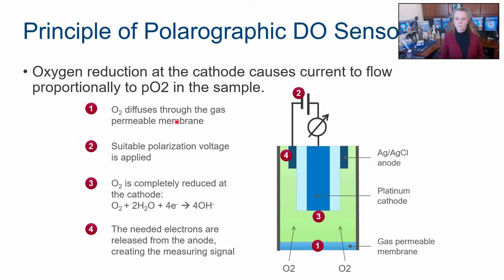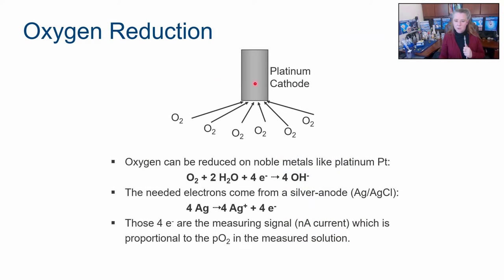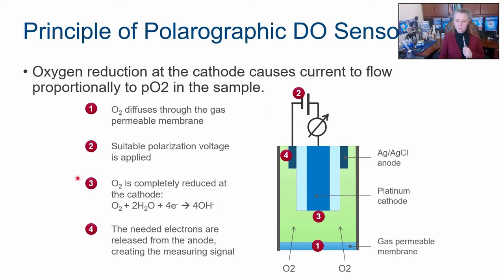So this is how a polarographic sensor works. You have all of this happening inside of a sensor. In this case, guess what? This is a polarographic sensor. Okay. So we have oxygen. It diffuses through a gas-permeable membrane, and there's liquid here. There's your electrolyte. We're applying a voltage across so that we can have all of this happening. We have a platinum cathode and a silver chloride anode. The chemistry we just saw here happens, and we end up with a current, a nanoamp current.